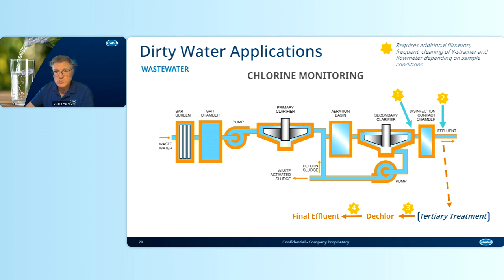Now we have other applications with dirtier water, such as the pre-disinfection chamber after the injection of chlorine, and the post-disinfection contact chamber, to provide closed loop control, for example, for the chlorine feed. Those applications may require additional extra time and effort to clean the Y-strainer and the flow meter. Now, we can talk a little more specifically about application number 4, the last one depicted on this slide, which is measuring the final effluent after dechlorination. This is where the chlorine concentration is extremely low, and therefore the instrument may suffer from biofouling. It's a very common issue with dechlorination applications.